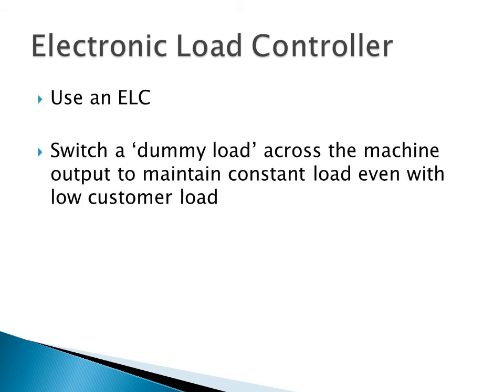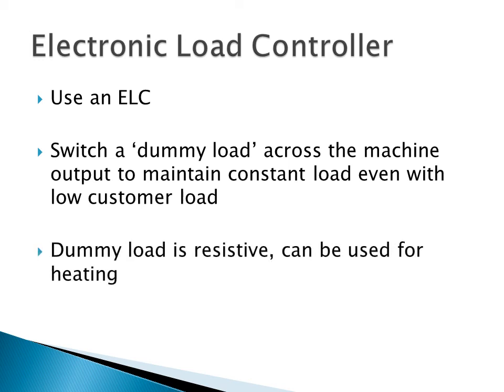We can use an electronic load controller. Basically, it switches a dummy load across the generator output to maintain a constant load, even when the customer load drops. It senses the voltage and switches across the dump load, or the dummy load, as necessary to keep the load relatively constant. And the dummy load is often resistive, and you can use it for heating water or heating an area. It could be lights, any sort of resistive load.